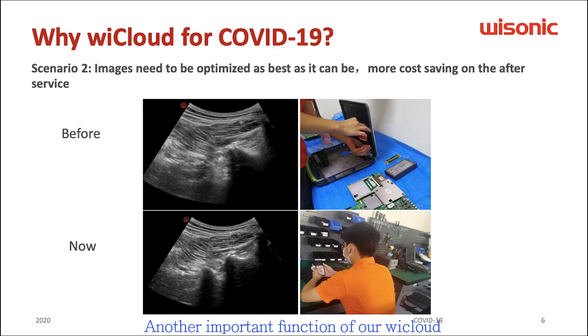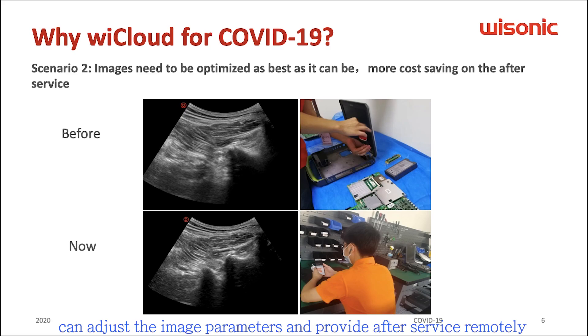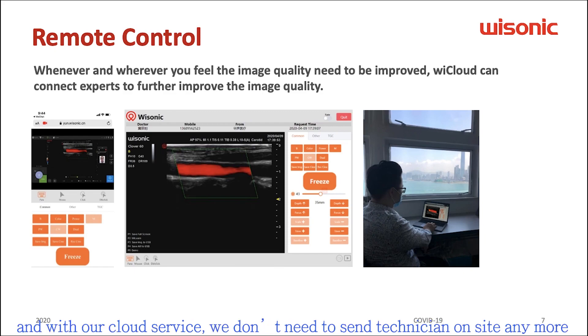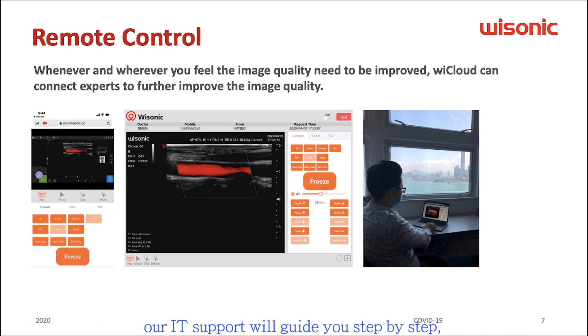Another important function of wiCloud is the ability to adjust image parameters and provide after-service remotely. You can adjust the gain, depth, dynamic range, and more. With our cloud service, we don't need to send technicians on-site anymore — our IT support will guide you step by step.